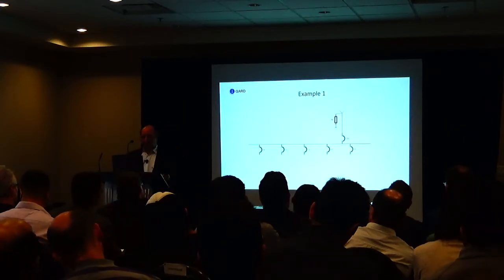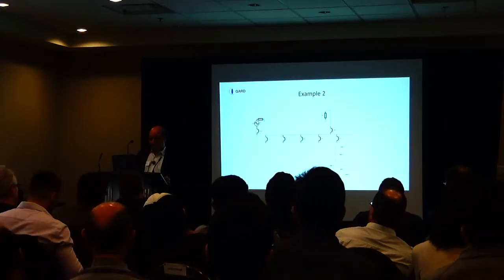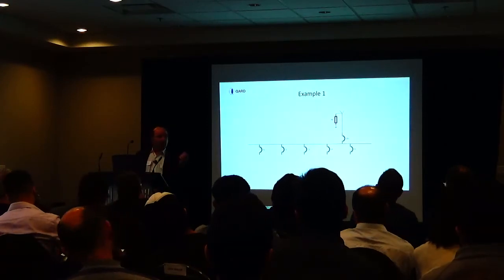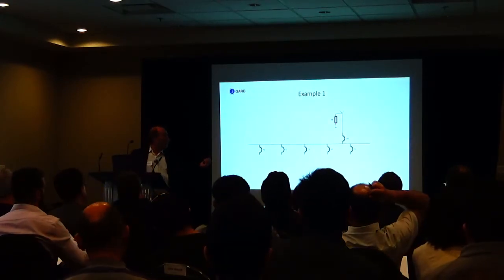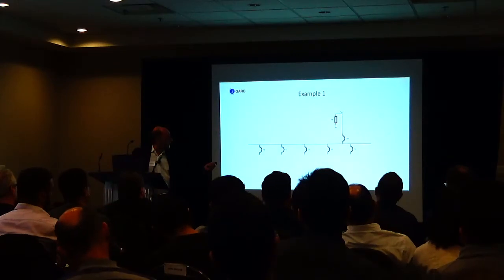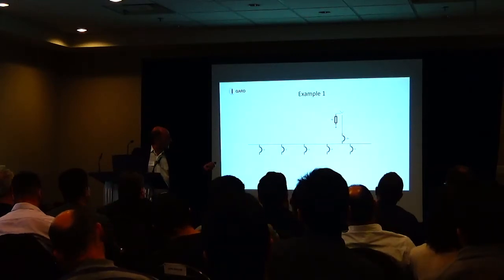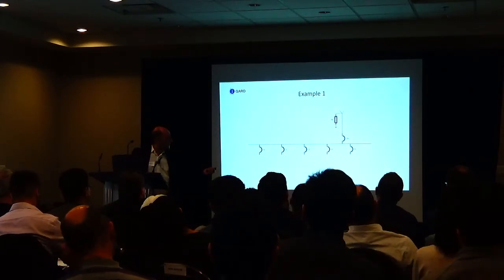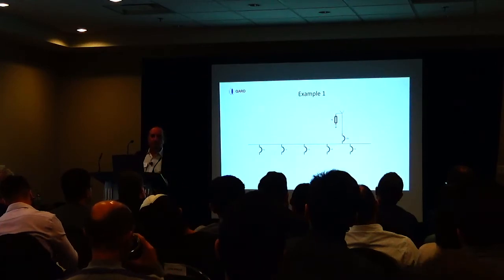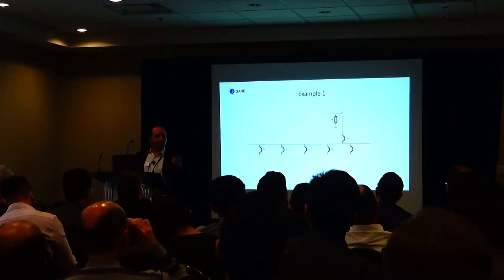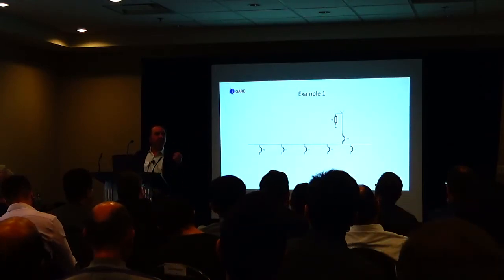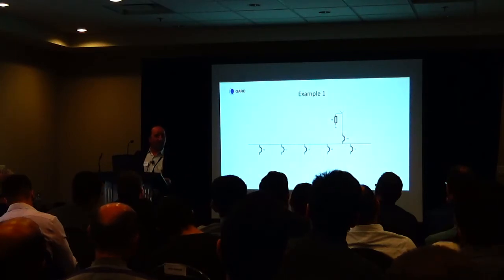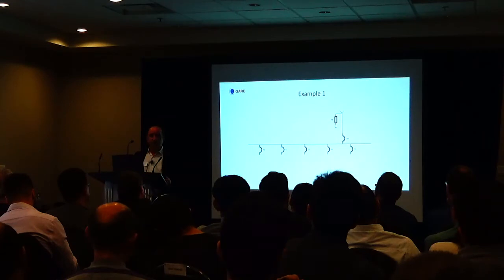We had one facility here where they had just that. Resistance ground in the system, transformer, resistor, and we put a ground fault on it. The 2 phases did not elevate, which means it was solidly grounded. We're getting 70 amps of current. And nobody commissions this kind of stuff before.